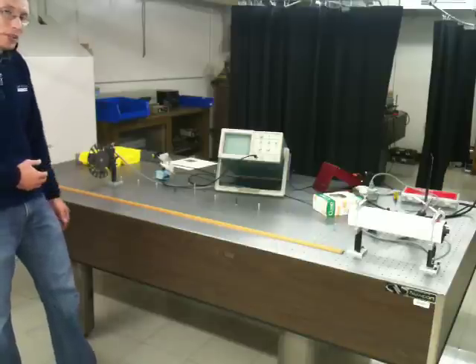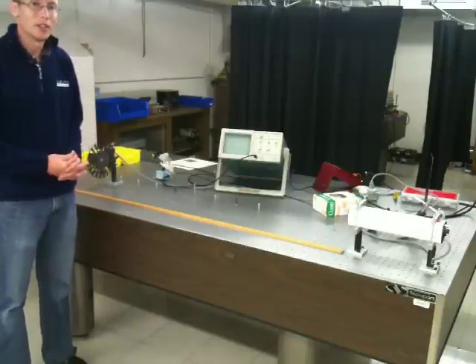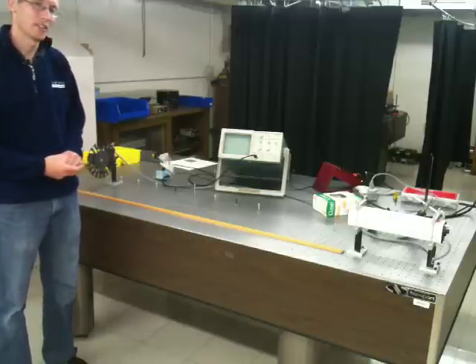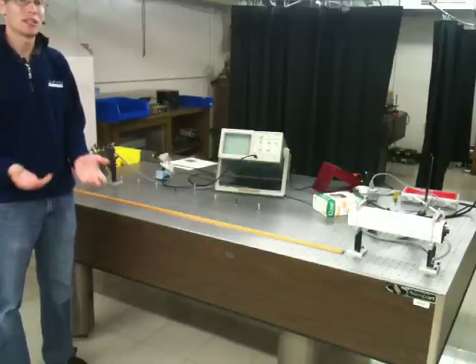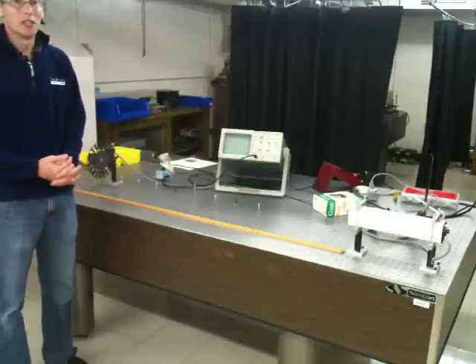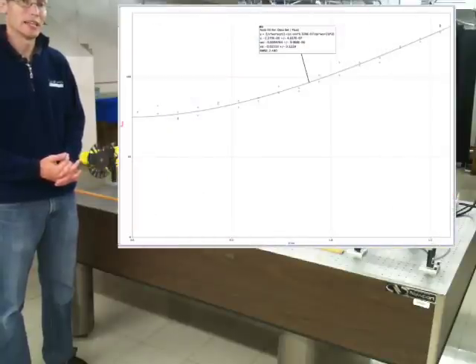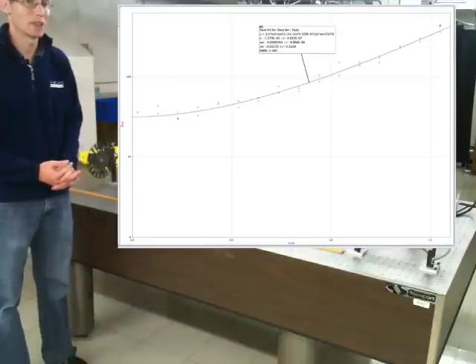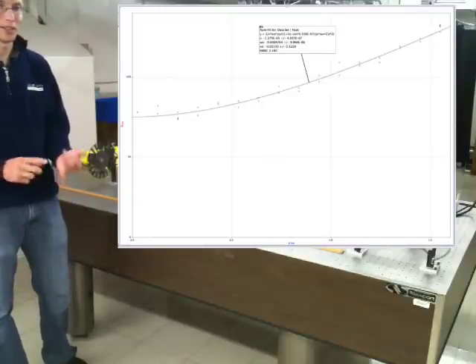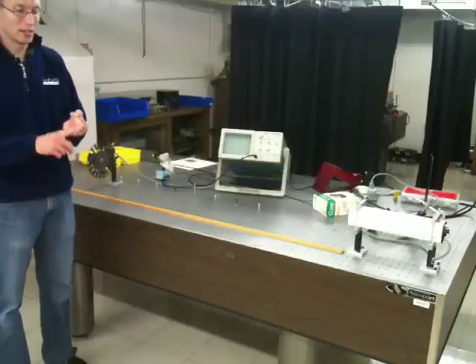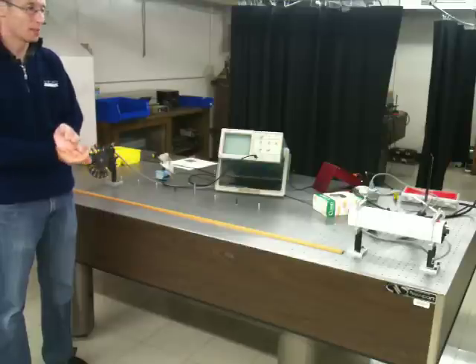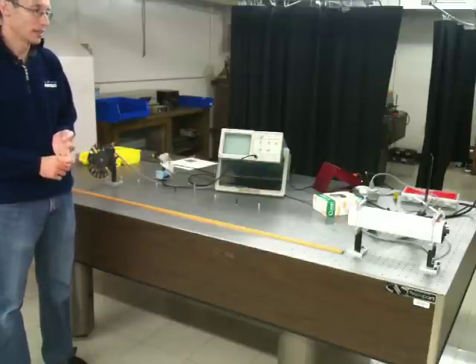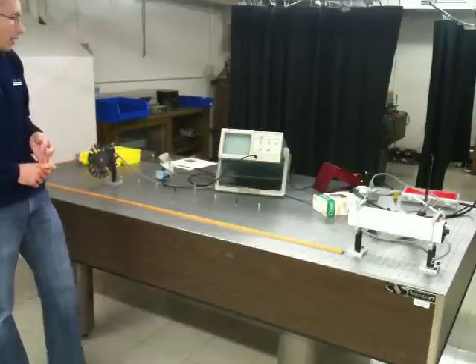And by doing so, I can trace out the Gaussian beam radius as a function of distance. And by using the formula for the beam radius as a function of distance, I can do a curve fit and determine the Gaussian beam parameters. That's the waist size and its location. And one other free parameter is the wavelength, but typically I have other ways of measuring that or knowing that so that I can fix that in my model.